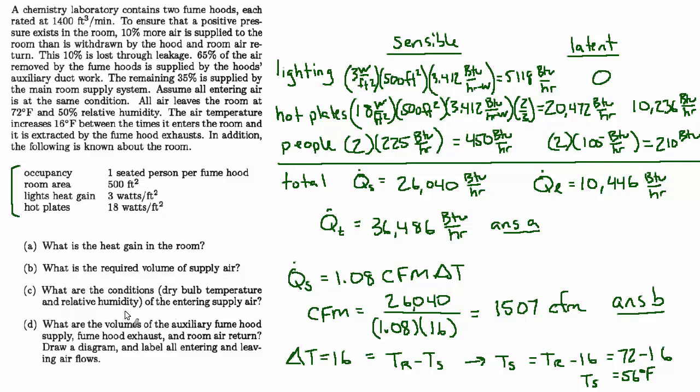But they also want to know the relative humidity, and that is considerably more interesting to calculate. Because we assumed that the required supply volume was based on the sensible load, and now we have to figure out how dry that supply air would have to be in order to absorb the amount of water vapor that's being added to the air by the latent load that we have, such that when it leaves it has these conditions: 72 degrees and 50% relative humidity.